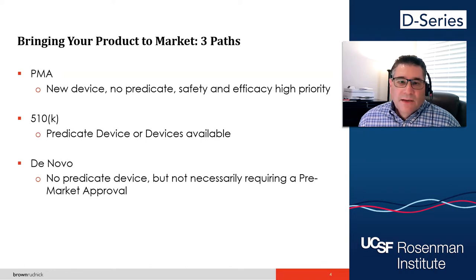Generally the 510K is considered a notice. So you file it and then you wait 90 to 180 days, and without comment from FDA, you can proceed using the device at risk if you don't hear from them. Most of the time you hear from them that your notice is accepted and you're authorized to put it on. But it's not an approval. It's a notice and authorization, and it's a shorter route.